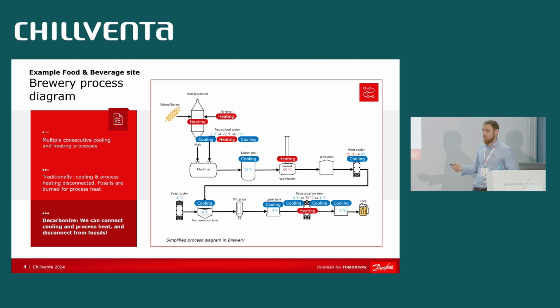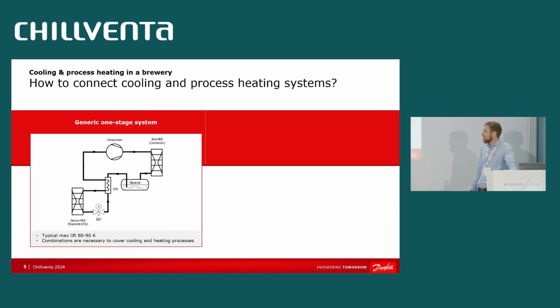But generally, why waste the heat? Why reject it to the ambient and not reuse it, not lift it to a higher level? Right? We talk about decarbonization of industry. So, which technologies can get us there? Well, let's start simple. We talk about cooling and heating, which means cooling down to negative temperatures, refrigeration, minus 20, minus 30 maybe. Well, not necessarily in a brewery, you don't go that low. But if you need to generate steam, you need very high temperature lifts.